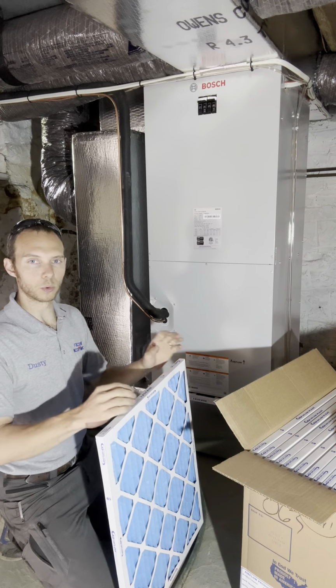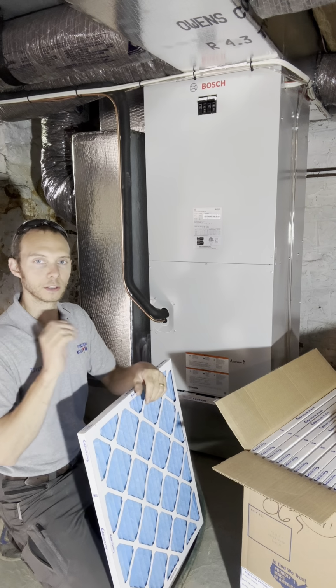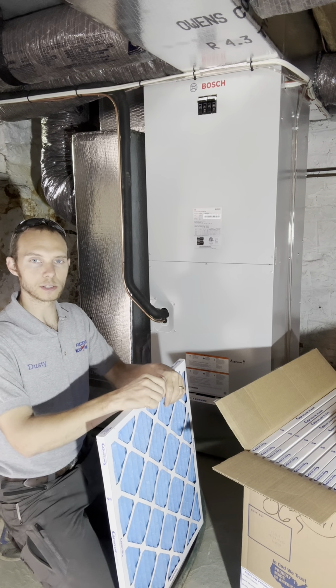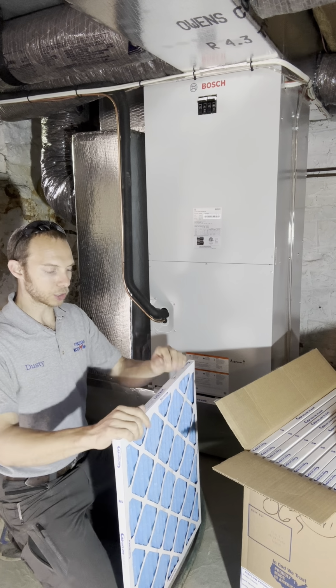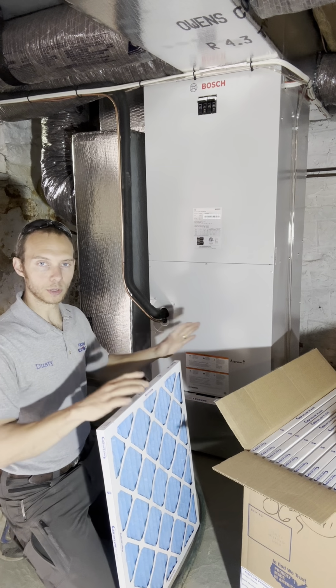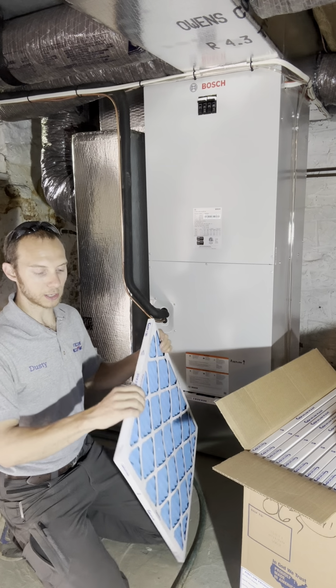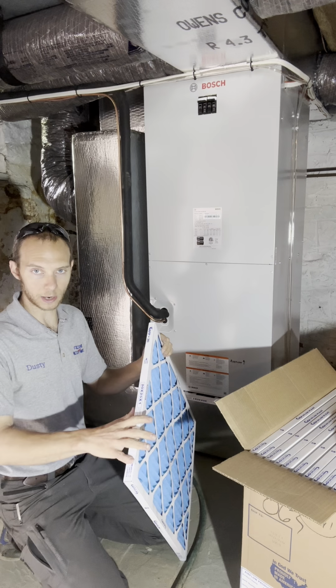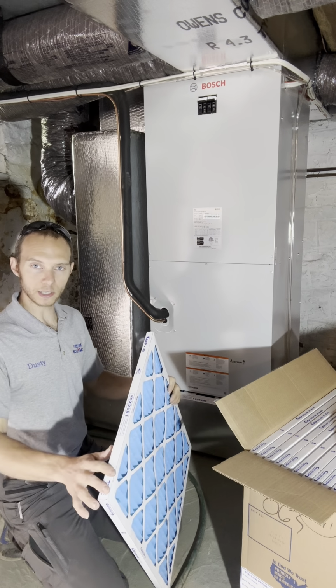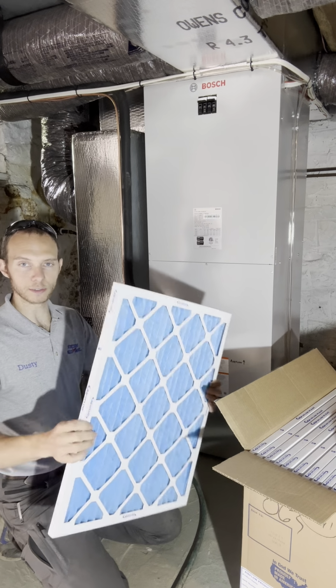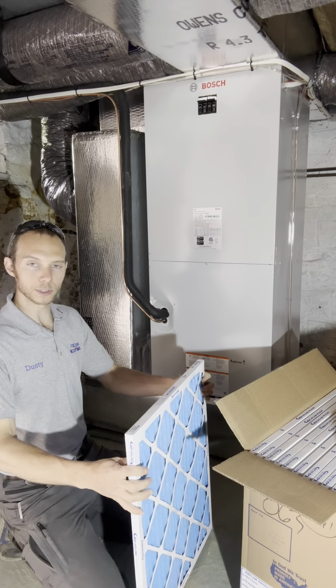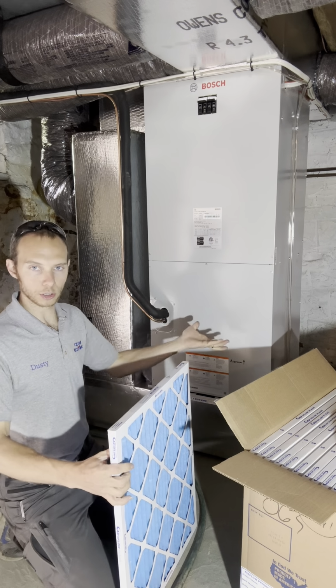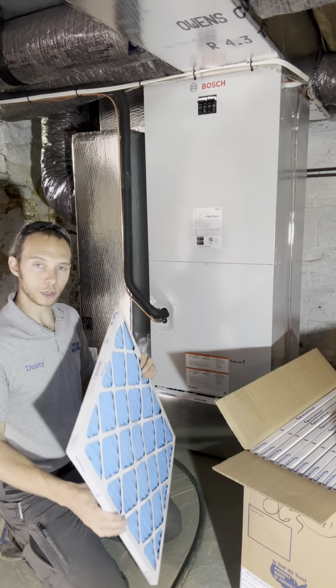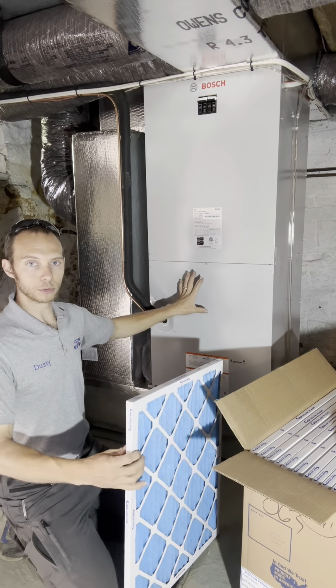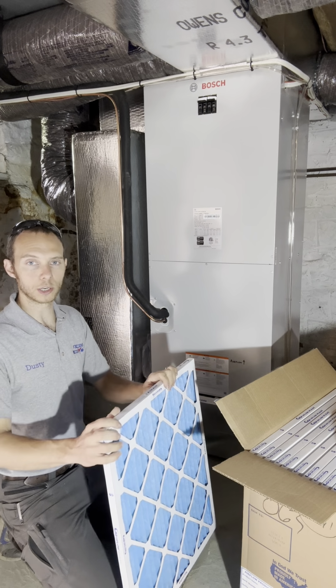You have to remember that coil is very fine as far as the passages in there. So we want to pay attention to what we're putting in the unit. We typically do not use anything lower than a MERV 10. And so that's the efficiency and effectiveness of the air filter itself. If you go too light, you're going to clog the coil. If you go too aggressive, you can also slow down the airflow too much in your system.